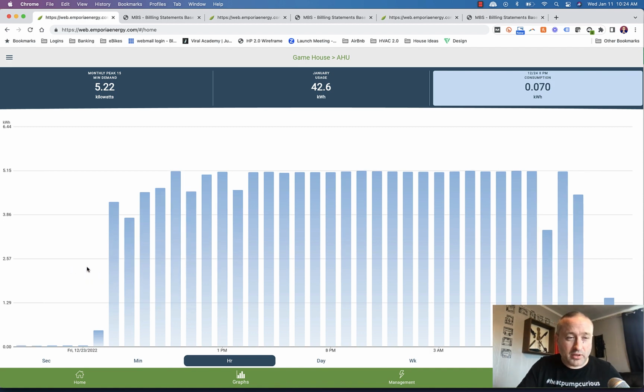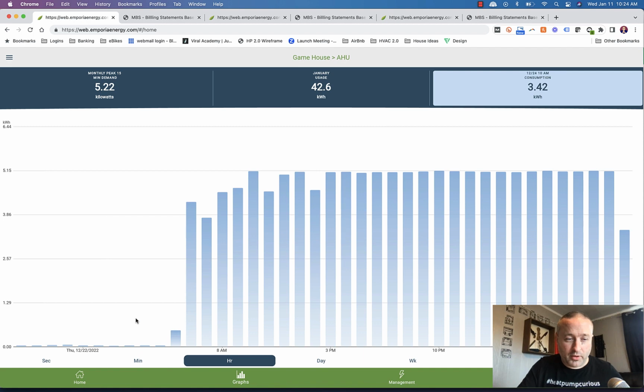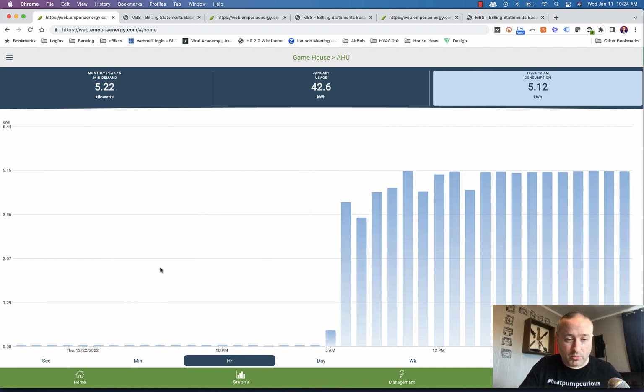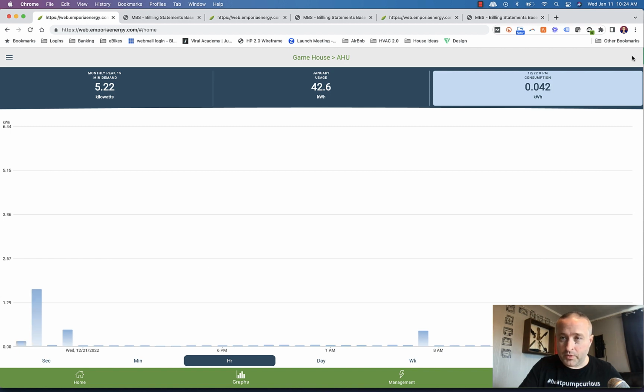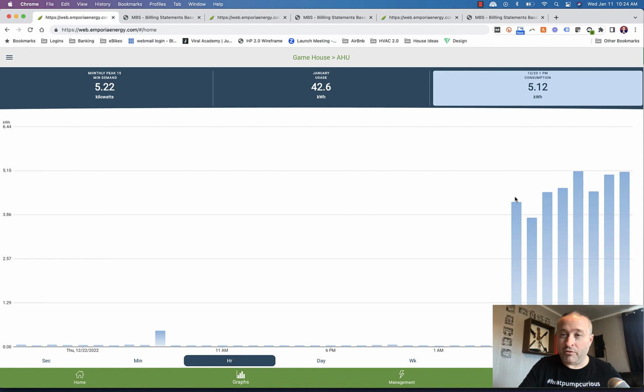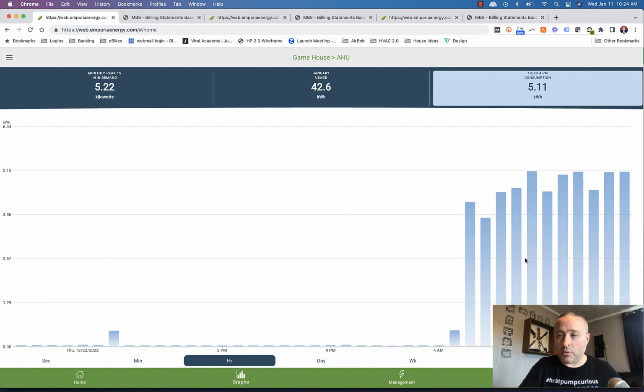So you can see, remember how I showed where the heat pump just stopped working? So you can see the air handler's using almost no power over here. So we're using 0.04 of a kilowatt hour per hour for the fan. And then all of a sudden, boom, we're using 4 and 5 kilowatt hours per hour. So this is the resistance hitting. And it almost kept up.